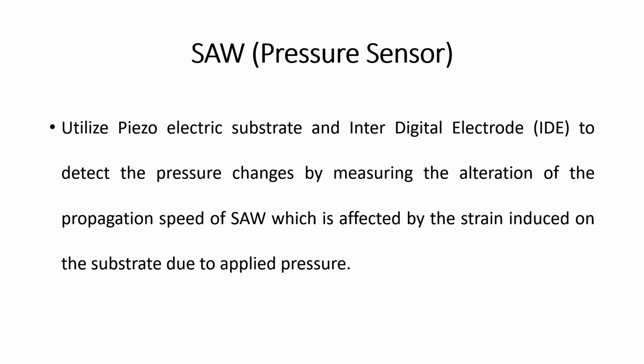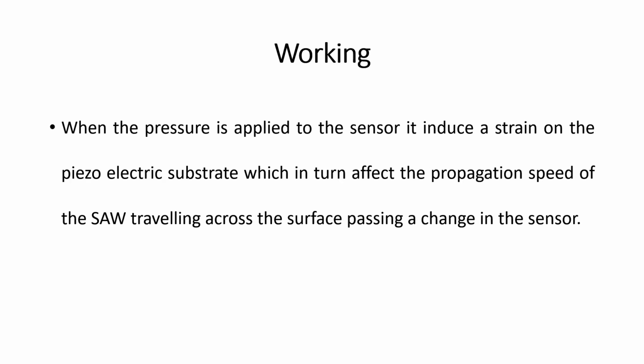SAW pressure sensors utilize a piezoelectric substrate and interdigital electrodes to detect pressure changes by measuring the alteration of the propagation speed of the SAW, which is affected by the strain induced on the substrate due to applied pressure. Working. When pressure is applied to the sensor, it induces a strain on the piezoelectric substrate, which in turn affects the propagation speed of the SAW traveling across the surface, causing a change in the sensor output.